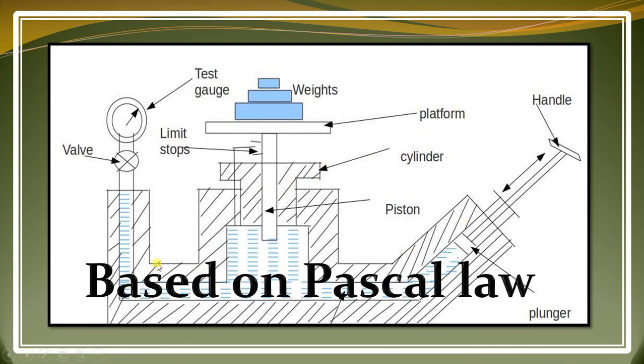Now let's talk about this deadweight tester. This deadweight tester is based on Pascal's law. And now what is Pascal's law? When we use an incompressible fluid in a closed system and apply a pressure on this and pressurize this fluid, it exerts force in every direction with the same intensity. Okay, so in this deadweight tester, here is the oil that is filled in this closed system. Here is a piston to compress this liquid and two ports, this piston and this valve. We can get the output pressure of this fluid, but both are the same because of this Pascal's law.